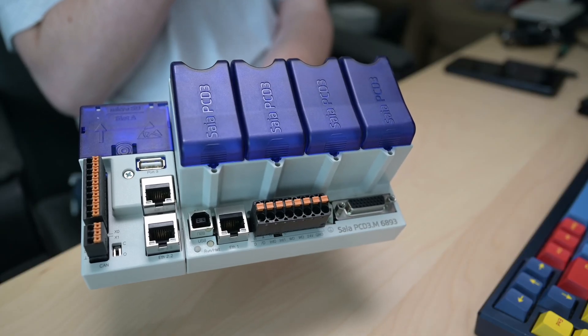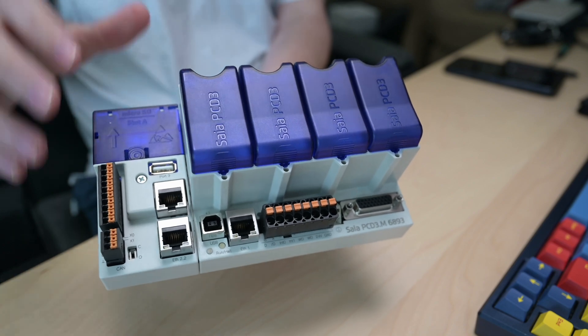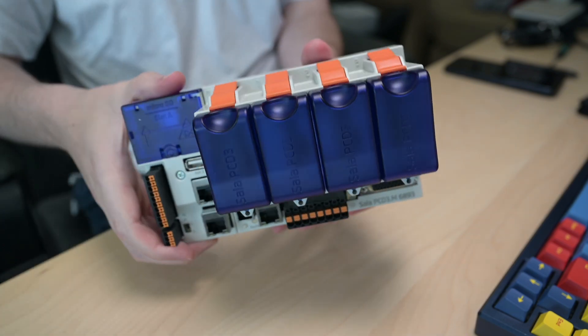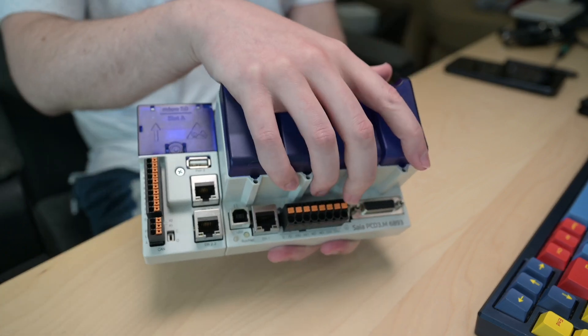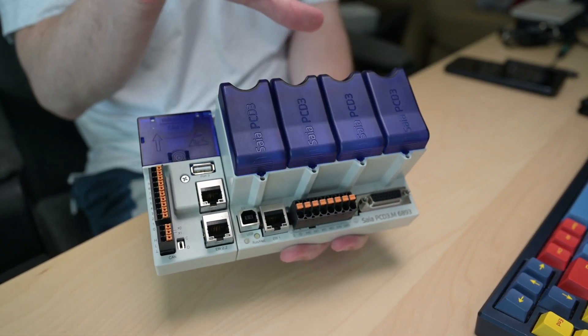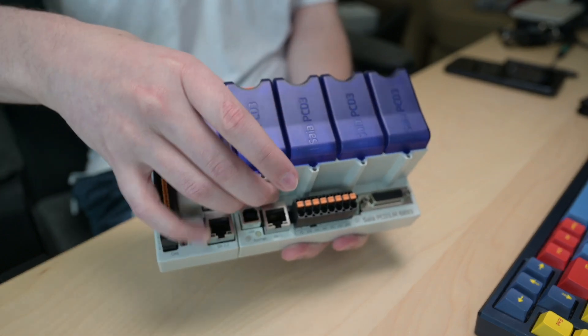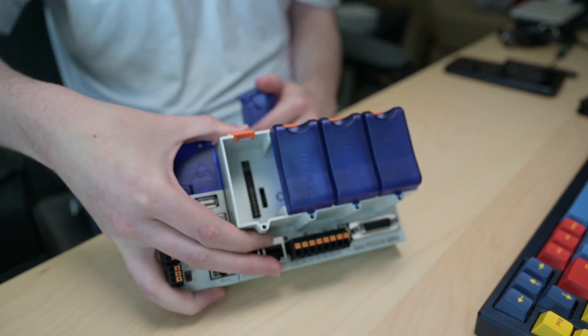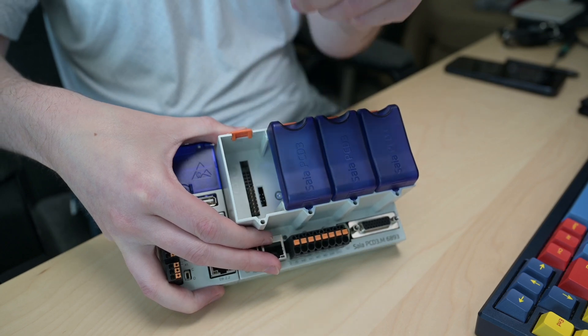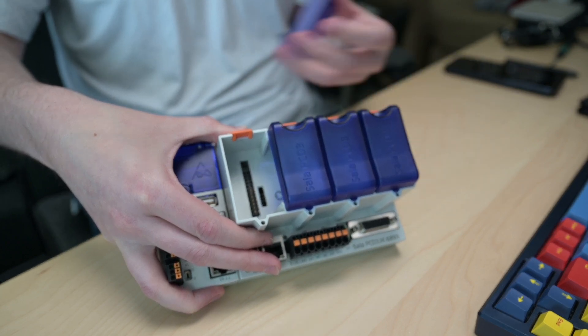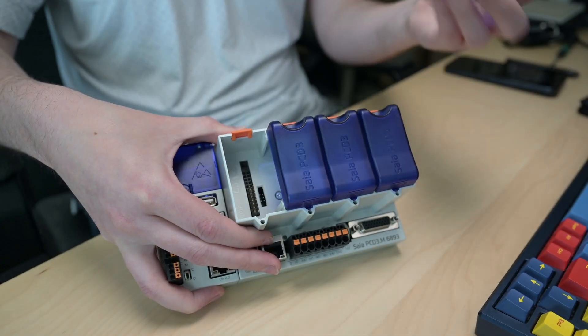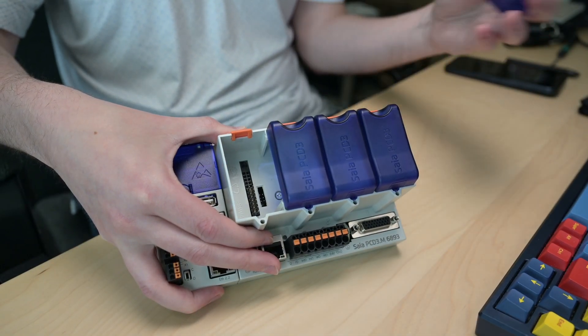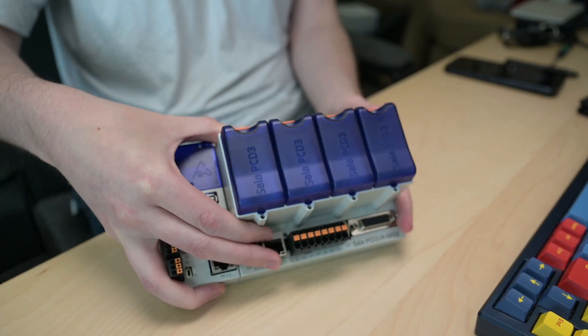Here we have the Saia-Burgess Controls PCD3.M 6893 PLC controller. The first thing you'll notice is these four slots at the top. This is what you're going to use for your IO modules. They'll pop in here if I hold that clip down at the top. Those will just slip in and you get the ability to mix and match as you need with your analog inputs, outputs, digital inputs, and outputs. They have the typical variants you would expect to see as well as options that have handoff autos if that's the kind of thing you need.